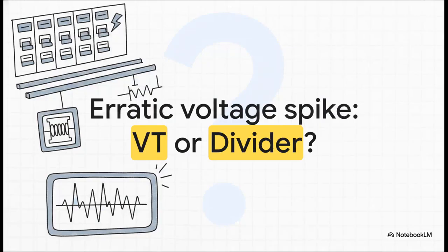Okay, let's test this out with a real-world troubleshooting scenario. Imagine you're standing right in front of the switchboard. A breaker operates, and immediately your busbar voltage reading spikes wildly and erratically on the display, and then it slowly settles back down to normal. Based on what we just covered, are you looking at an installation using a traditional VT or a resistive divider? Think about it for a second.